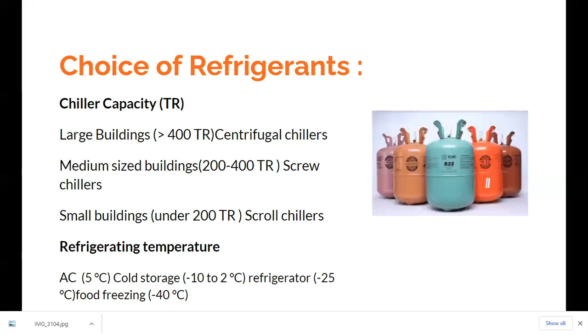One very important thermodynamic property which has to be kept in mind is the normal boiling point. The normal boiling point is the temperature at which the refrigerant would boil, provided the pressure is the normal atmospheric pressure. That is the reason why it is called the normal boiling point. The other important thermodynamic property is the freezing point. Evaporator pressure and condenser pressure are known as working pressures. These are very relevant when you select a refrigerant. A proper normal boiling point would ensure that the corresponding evaporator pressure and condenser pressure are also in range.